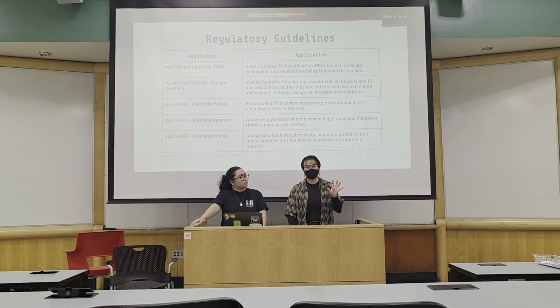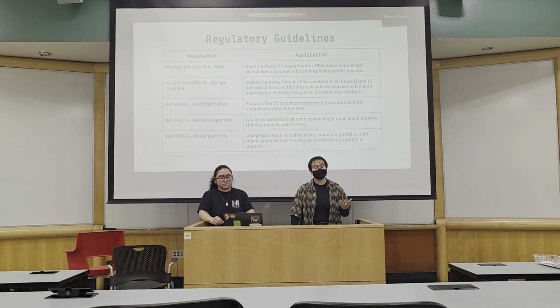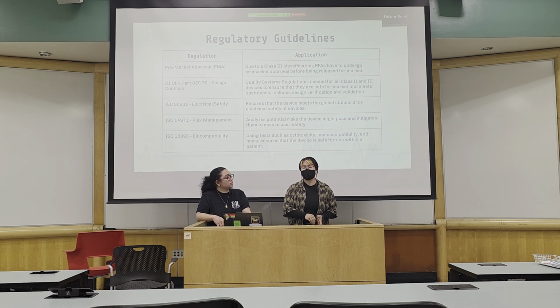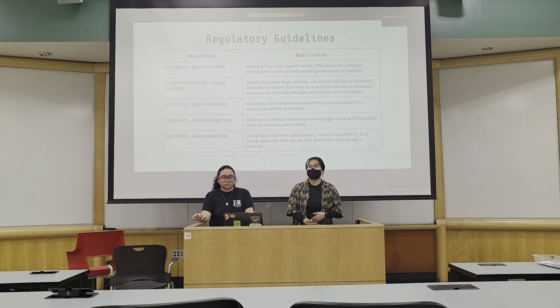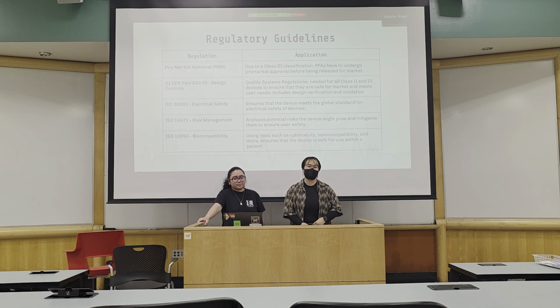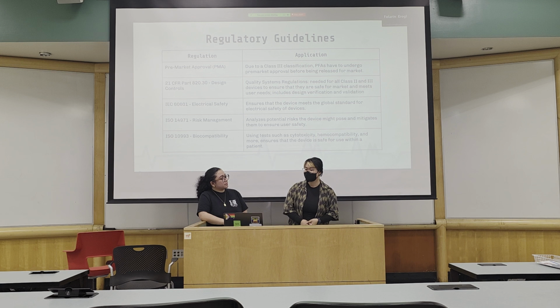Also, the standard regulatory guidelines that most medical devices have to go through also apply to PFA technology. So things like design controls, making sure that the quality of the device overall and the technology being used is properly documented, and also that risk is being assessed and mitigated before it goes out to market, because this is a potentially dangerous device. Also making sure that the design is verified and validated to make sure that it is actually going to do what it says it's going to do, and actually improve the quality of life for patients and improve the surgical efficacy for treating AFib.